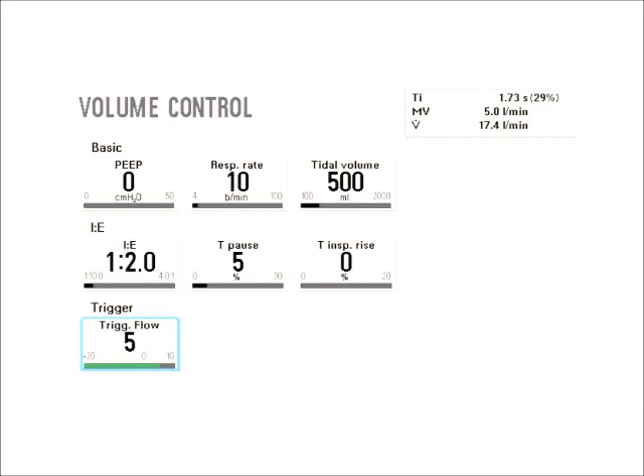I am going to use an example of volume control ventilation. During volume control ventilation, I have an inspiratory and expiratory phase. My inspiratory and expiratory phase is based on an inspiratory time setting, an IE ratio setting, or percent inspiratory time. As you notice from this picture, you can see the settings — I have an IE ratio, so a percentage of my breath is going to be inspiratory, and the other percent is going to be expiratory.